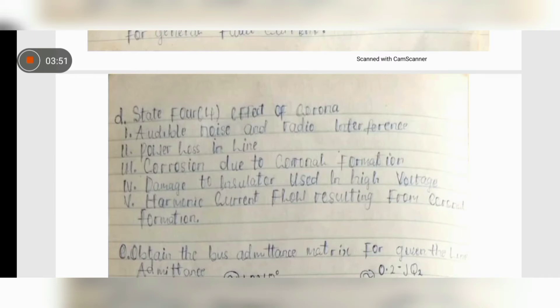State four effects of corona. Some people will be thinking corona is coronavirus. No, no, no. We also have corona in electrical power which we are going to be looking at very soon. We have number one, audible noise and radio interference. Number two is power loss in line. Number three is corrosion due to corona formation. Number four, damage to insulator used in high voltage. Number five, harmonic current flow resulting from corona formation.